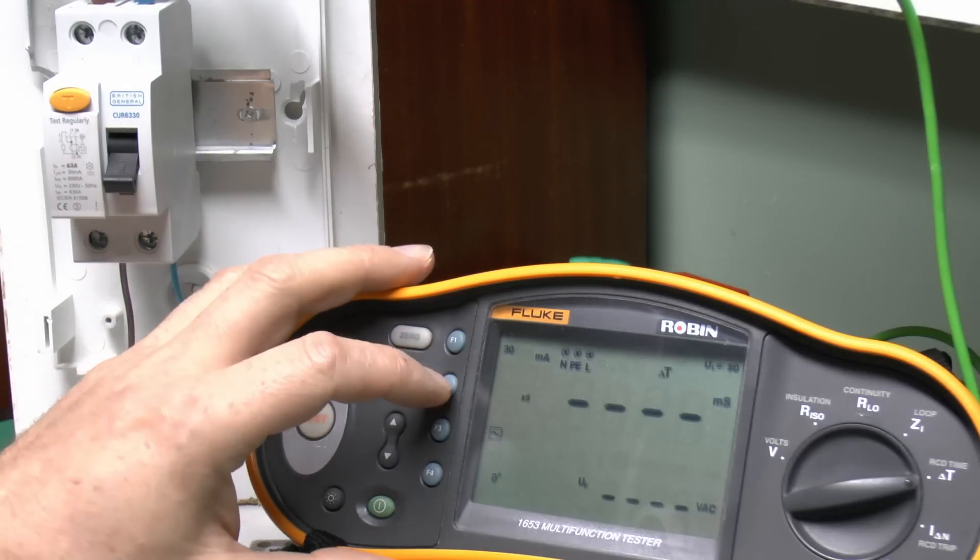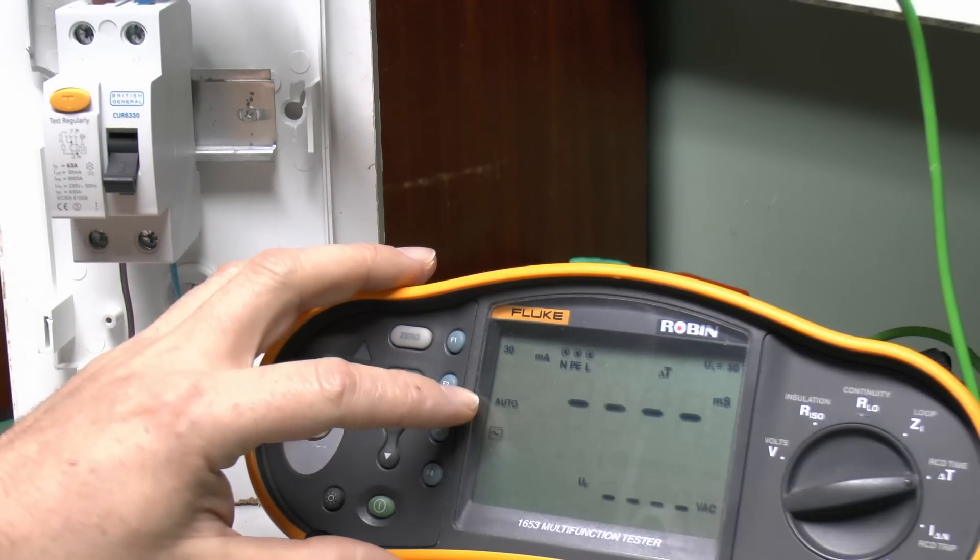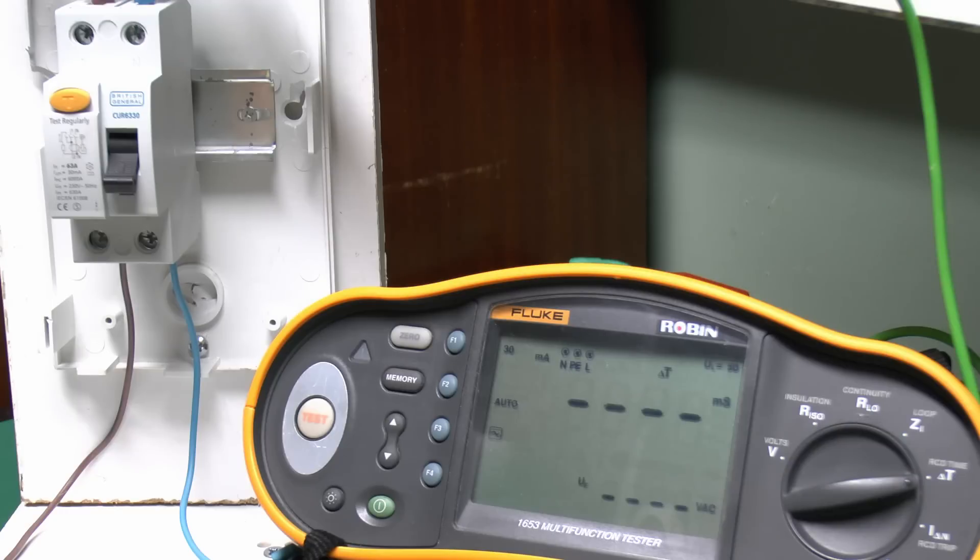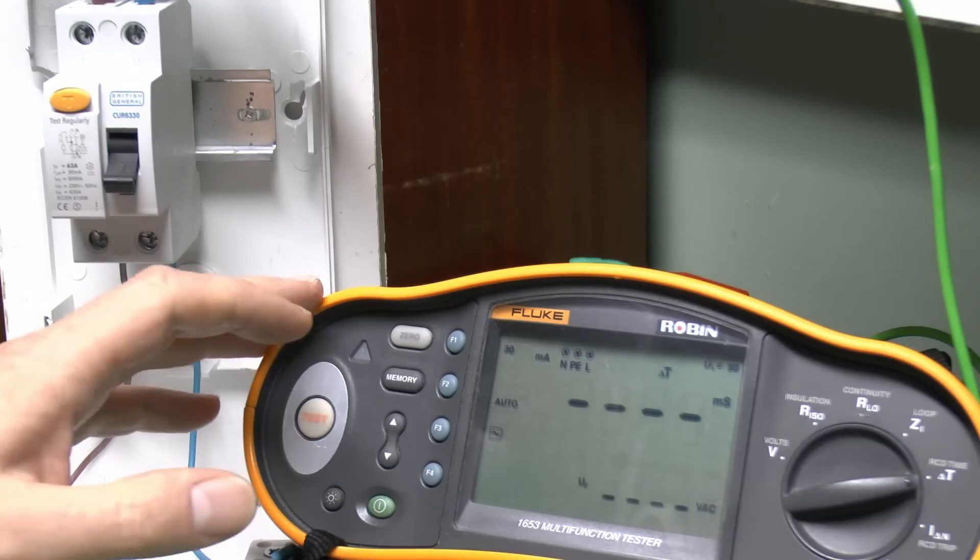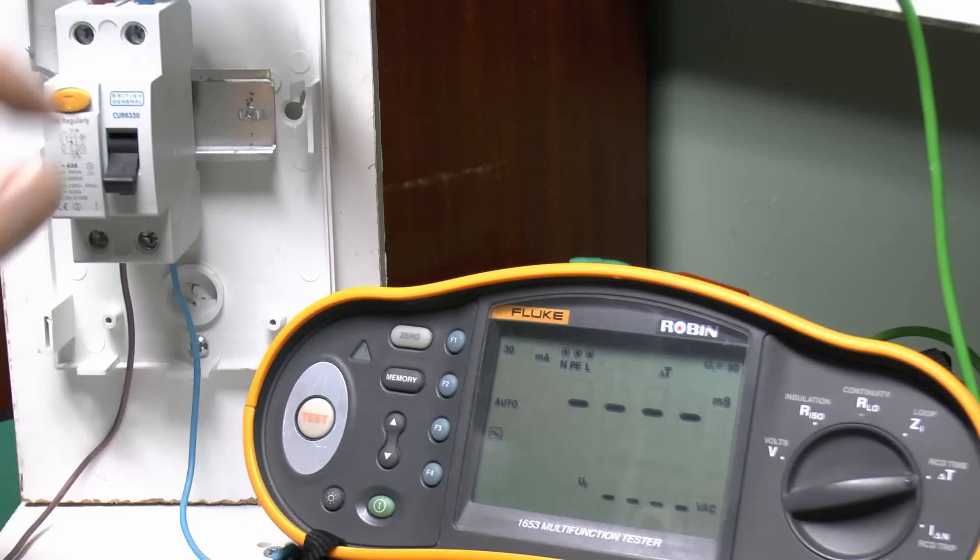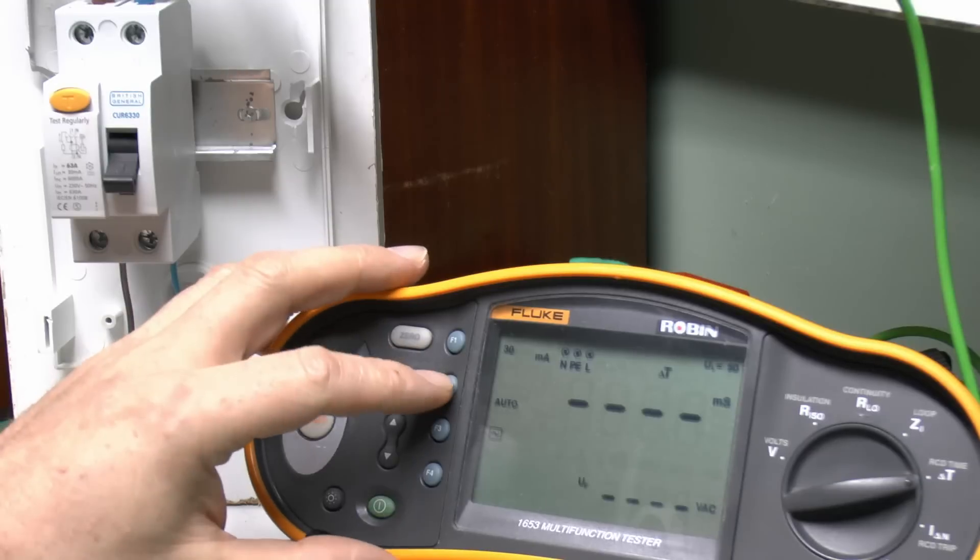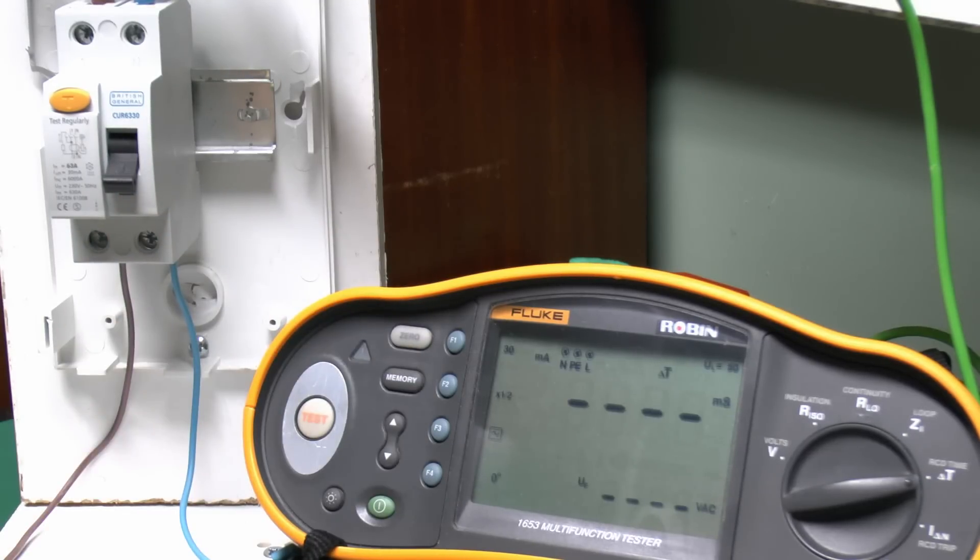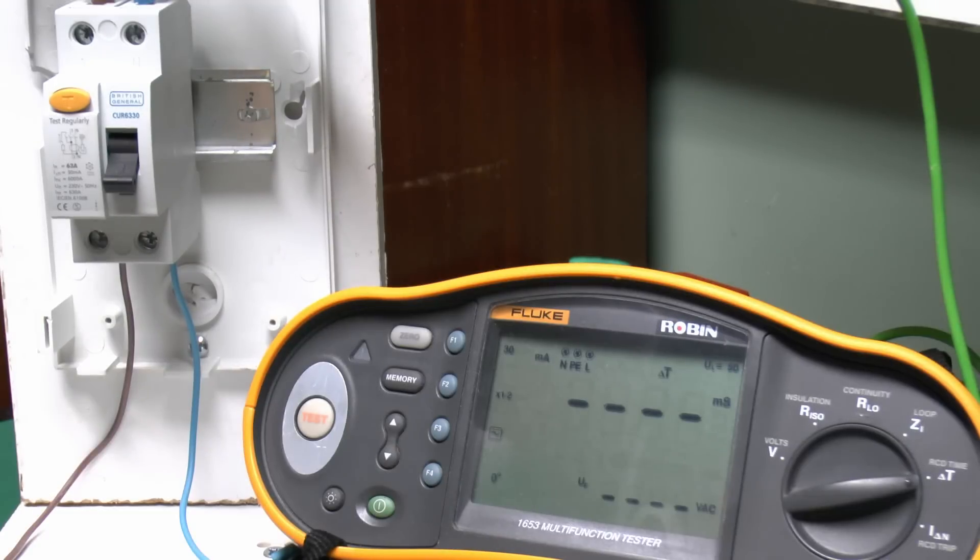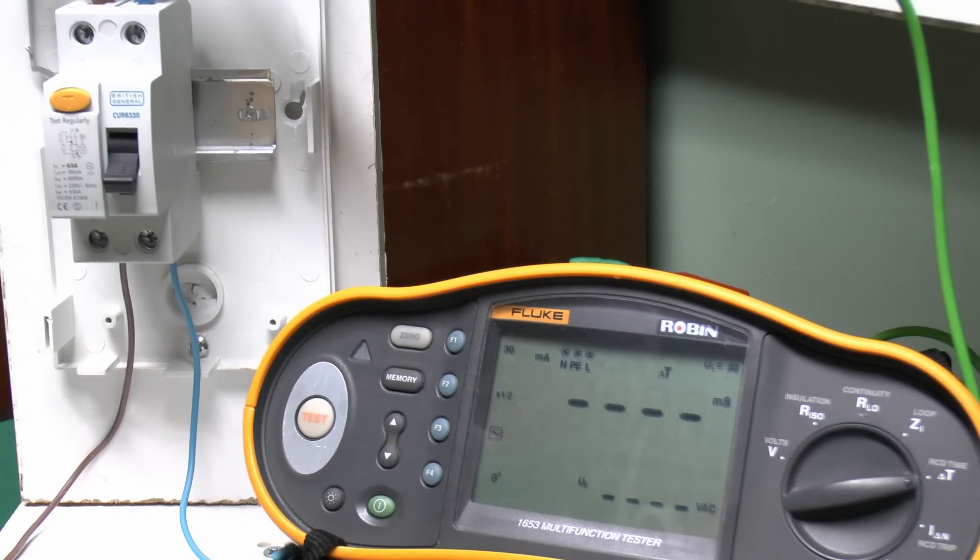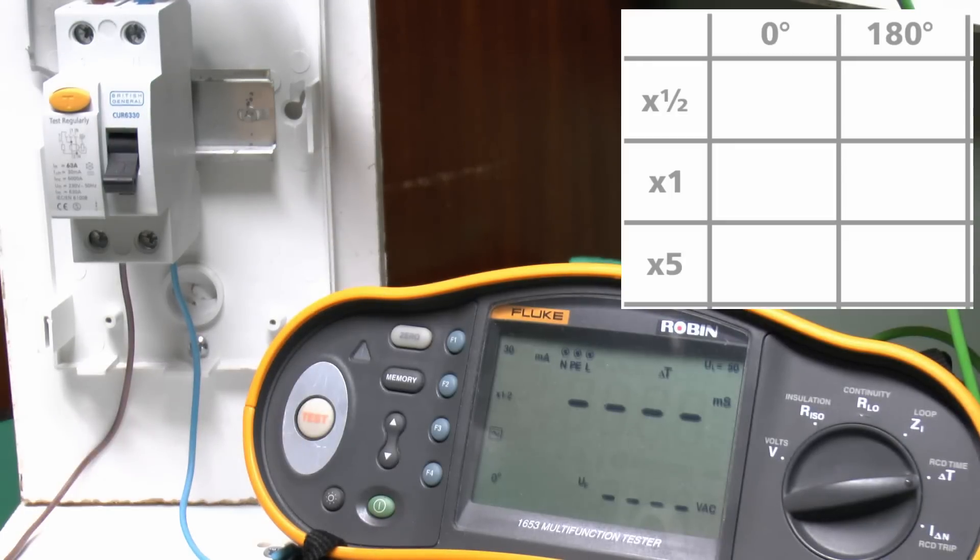This machine, and many others, have what's called an auto setting. And essentially, that just goes through the six combinations of current and 0 and 180. And it means you can just set this up, set it going, and then simply switch the thing back on multiple times, and it will automatically go to the next set of test settings. However, for this demonstration, we'll do them all manually, because that's a bit more instructive. And as it goes through, it will actually, on the auto setting, record all the readings internally, so you can scroll through them later. But of course, the easiest way is just to write them down with a pen on a piece of paper.